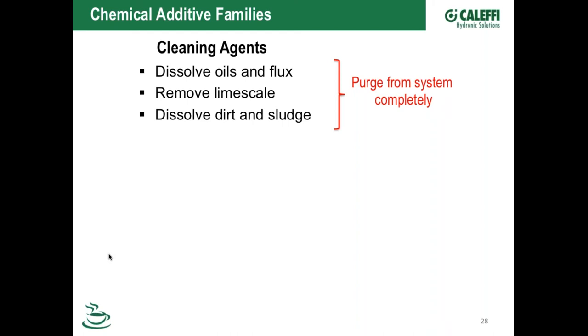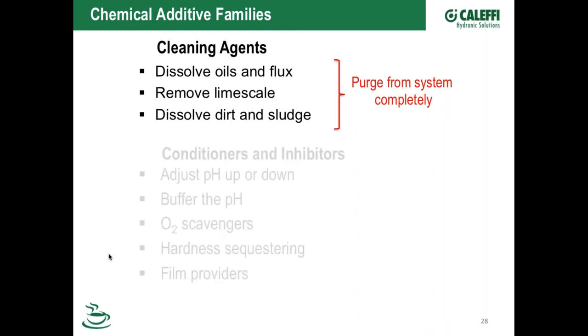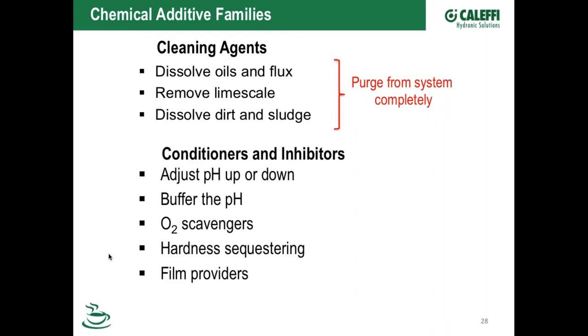He said it takes a lot longer than you think to get all that stuff washed out of the far extremes of your radiant loops and whatever might be in that building. Sometimes it takes hours to run enough water through there to make sure you've got the cleaners flushed out before you put in your good water, your chemicals, your glycols, or whatever you're going to use. So basically what the conditioners are going to do then, if you go that route, is buffer your pH.